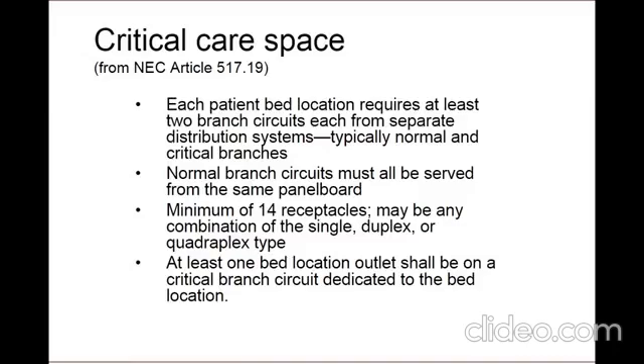The branch circuit minimum quantity and source requirements in a critical care space is the same as a general care space. The quantity of required receptacles is stepped up to 14 receptacles. In addition, at least one of the critical branch receptacles must be on a critical branch circuit dedicated to the individual patient bed location.